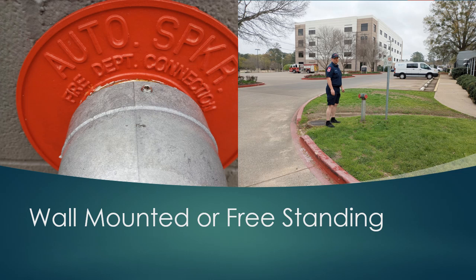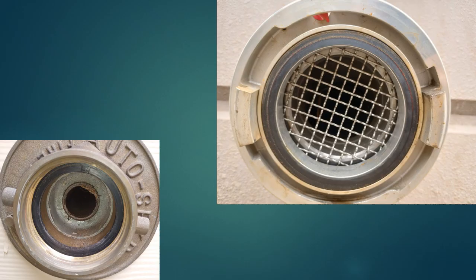Back plate on the FDC, the one on the left, I was telling you that it feeds an automatic sprinkler only. If you're looking at the intake on the FDC, you remove the plug, the cap, or the Storz fitting. You should look on the inside and make sure that there's a gasket and that it's unobstructed. This one has a stainless steel mesh in there to help prevent people from placing things in there that would obstruct the flow.